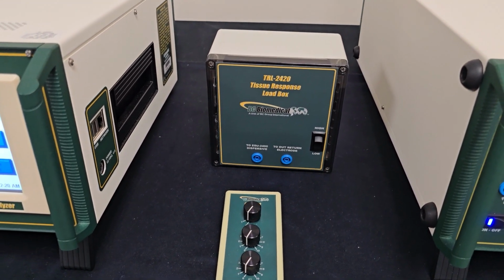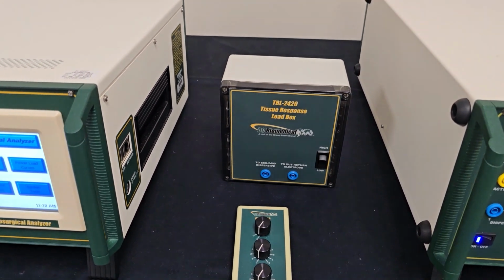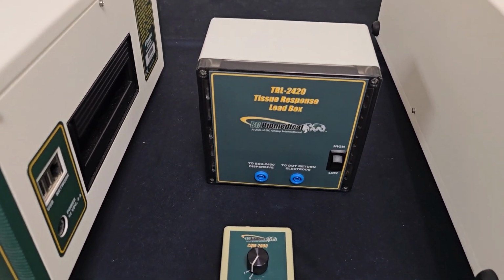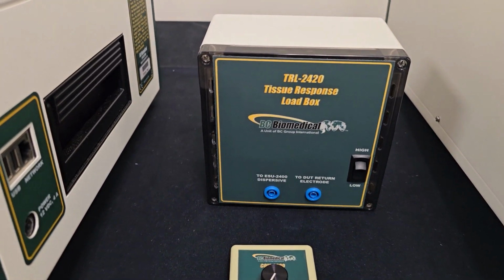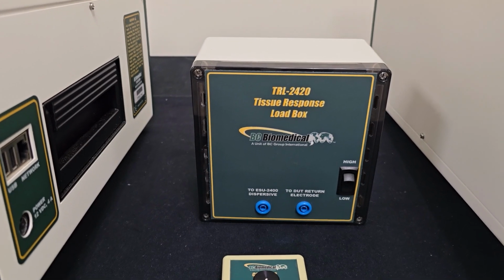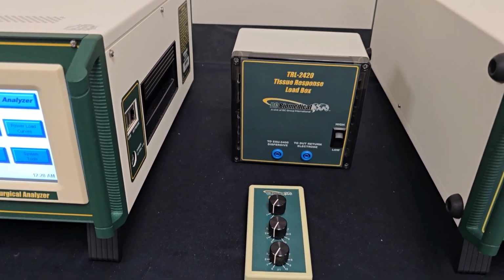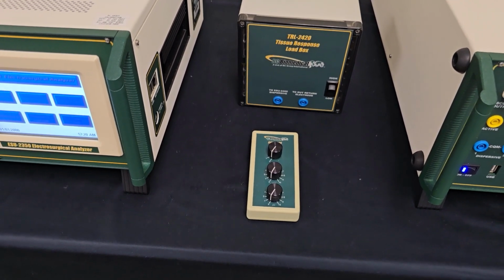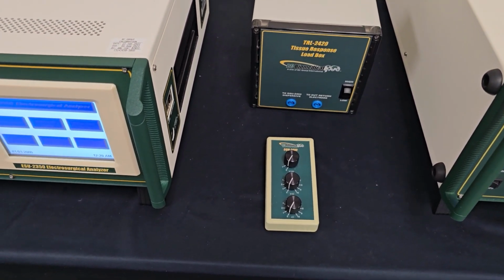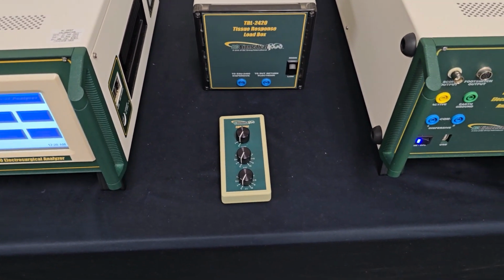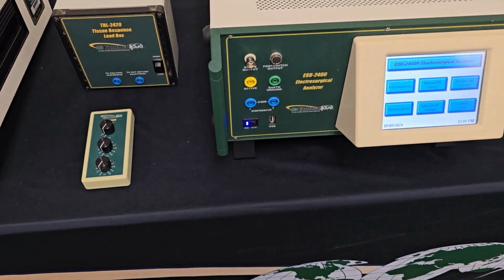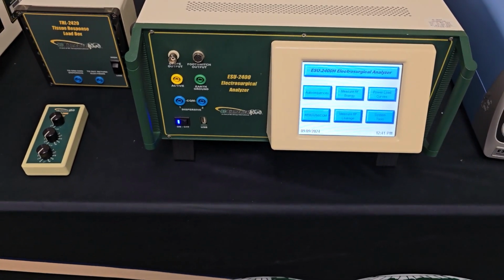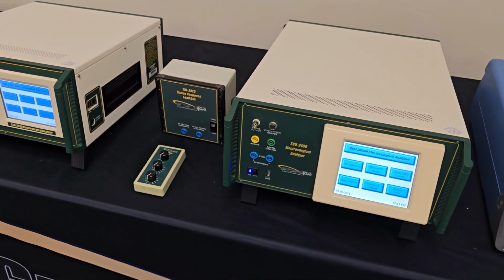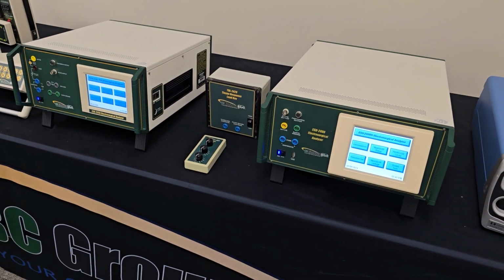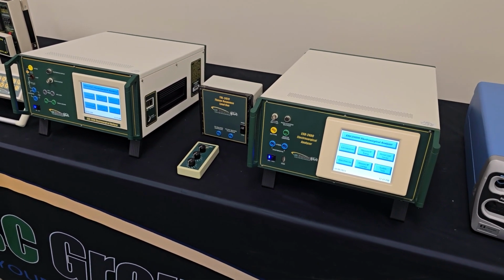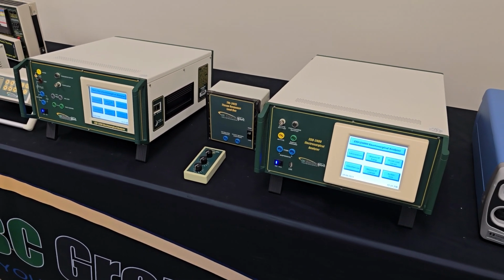I've never seen that before. So that's an interesting one. That was a special design for the Force Triad by Medtronic or Covidien. They actually used a light bulb to simulate tissue for the LigaSure vessel sealing test. Yeah. And so what we decided was, rather than just have a light bulb sitting out in the room, why don't we put it in a box and make it adjustable? So there's two different loads in there. One is for simulating a fault during a LigaSure, and the other is to simulate a sealed vessel. So that box allows you to do that.